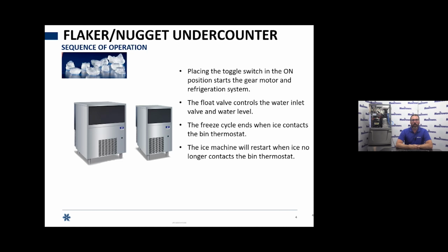The key takeaway is that we're not using a control board here. We don't have sophisticated sensors or control systems that we need to diagnose. We basically have safeties that are tied in series, and if all those safety conditions are met, we're up and running and in business. But there are a few differences between some of the machines, so we'll go through a few from each different category.